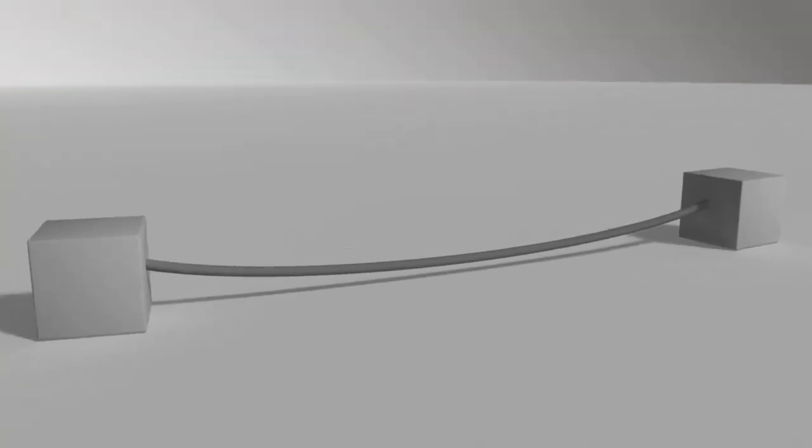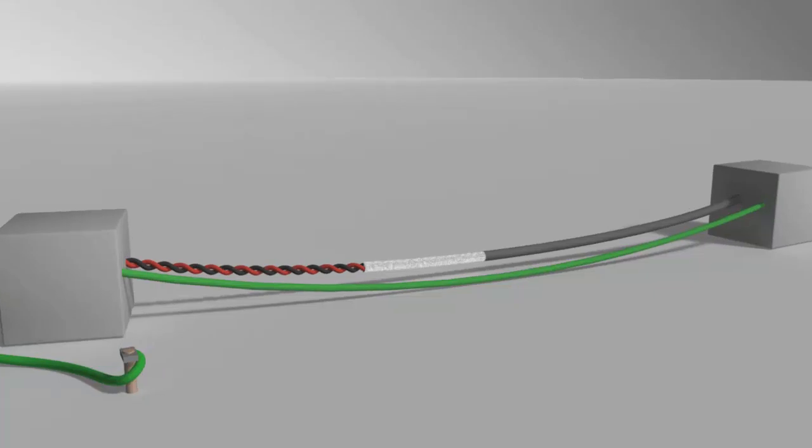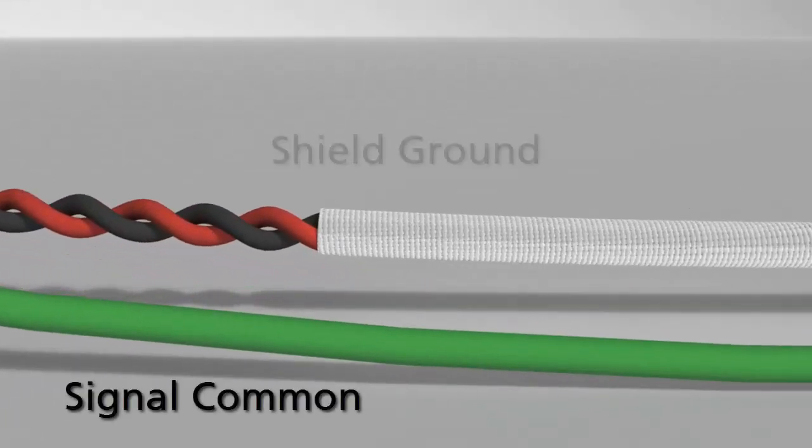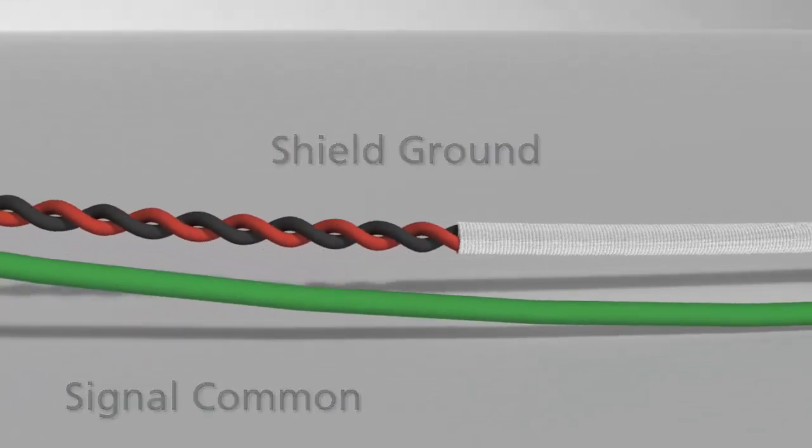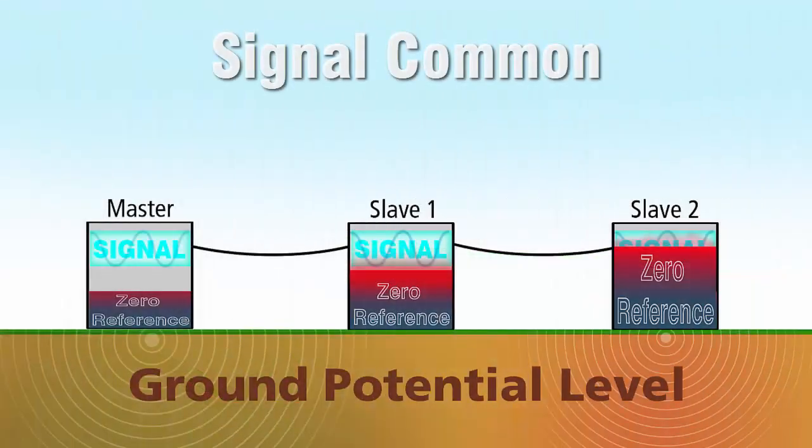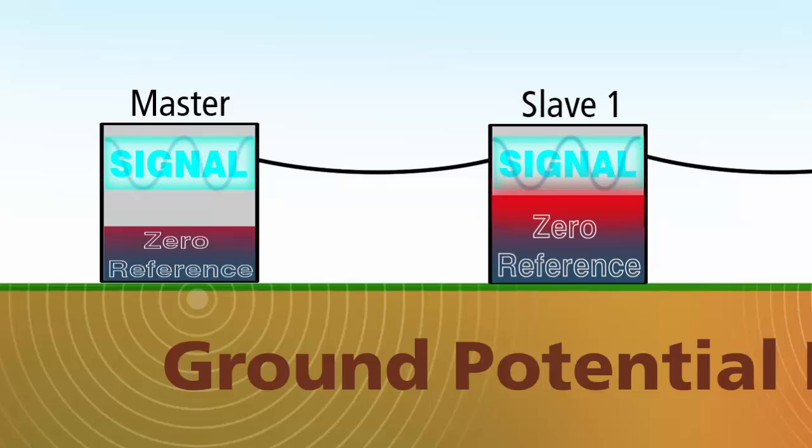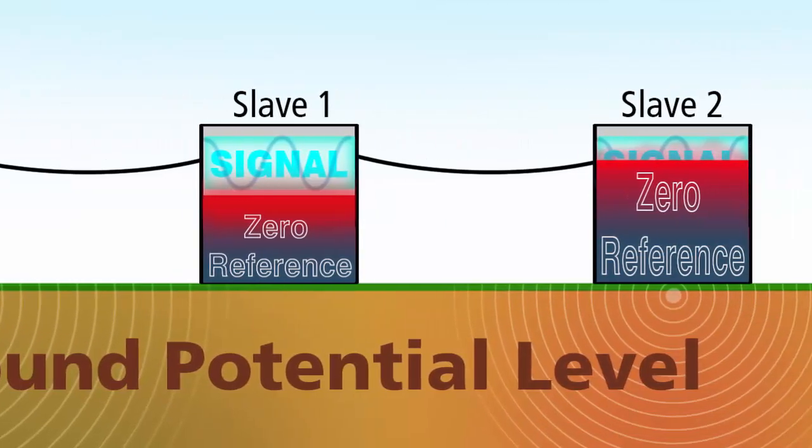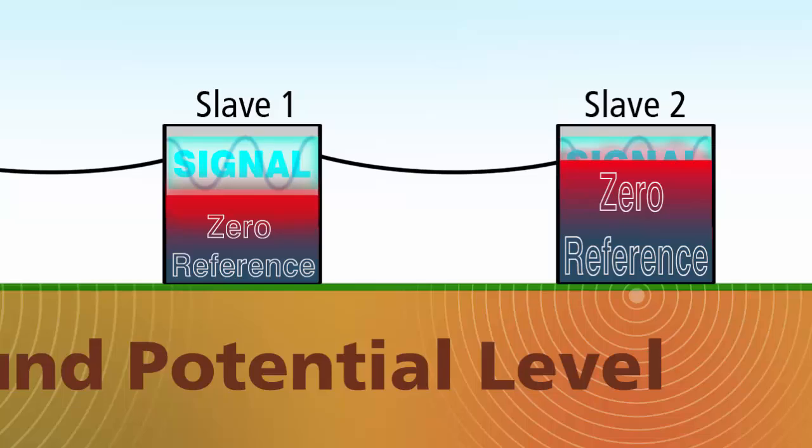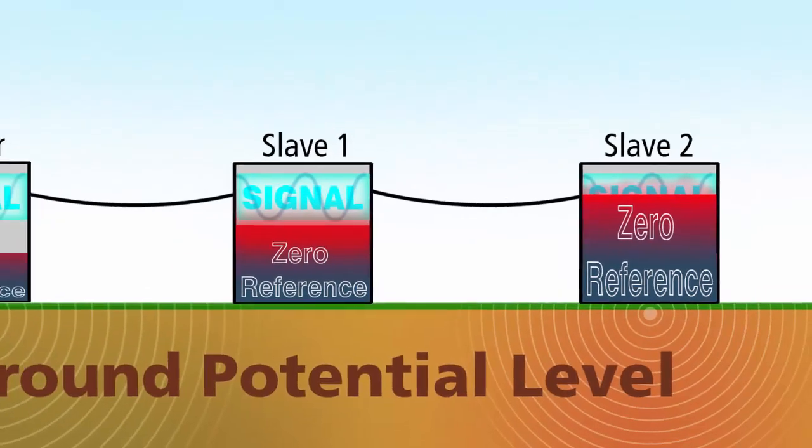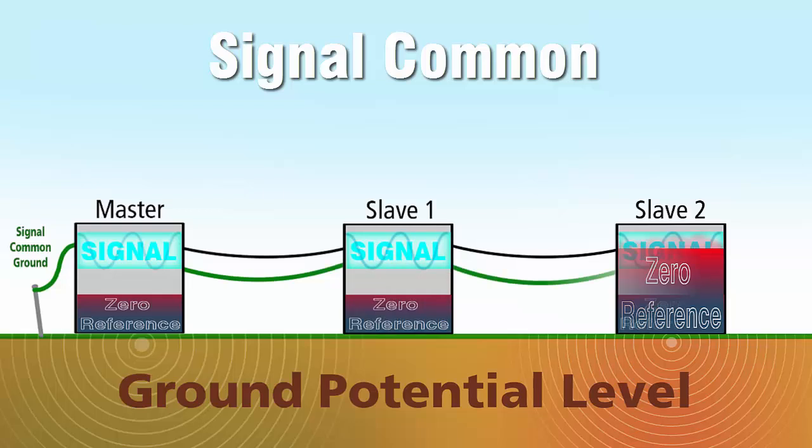To solve this problem, or at least fight against it, RS-485 networks utilize a signal common wire and a shield ground. The signal common wire runs, along with the signal wires, between each node on a network. It provides a common reference potential level for the RS-485 nodes, which otherwise carry floating voltages.